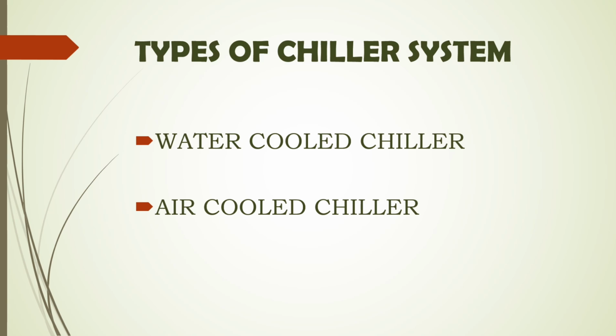Both water cooled and air cooled chillers are used in different scenarios based on factors like cooling capacity, space availability, water access, and energy efficiency. Water cooled chillers are preferred for larger buildings, industrial plants, and applications requiring high efficiency. The air cooled chillers are ideal for locations where water availability is limited or where easy installation and lower maintenance are priorities. Using both together is rare but can be seen in facilities with seasonal variations, switching between air cooled and water cooled systems for efficiency, large operations where backup cooling is necessary, etc.